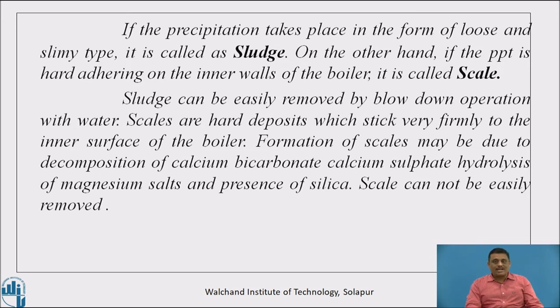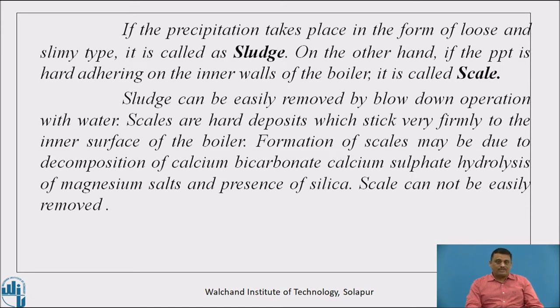Sludge is the initial stage of this process — due to evaporation of water, solids are thrown out and the initial loose precipitation is known as sludge. If the boiler is used continuously, the saturated salts increase and convert into a hard permanent deposit known as scale. Sludge can be easily removed by blow-down operation with water. Scales are hard deposits which stick very firmly to the inner surface of the boiler. Scale formation may be due to decomposition of calcium bicarbonate, calcium sulphate, hydrolysis of magnesium salts, and presence of silica.